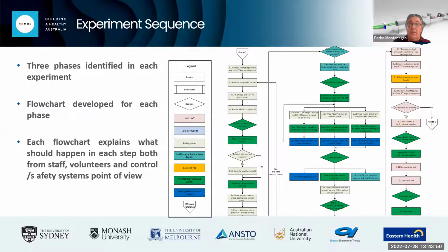The beamline staff phase is us with a lead that is clearly identified for preparation that will prepare the beamline for the imaging. And the way this is done is that, say, if it was me, my first step would be to go to the first enclosure, put the clinical mode beam stop in position and remove that key.